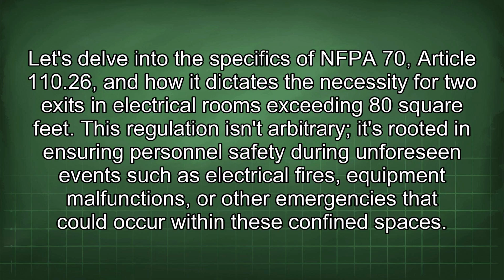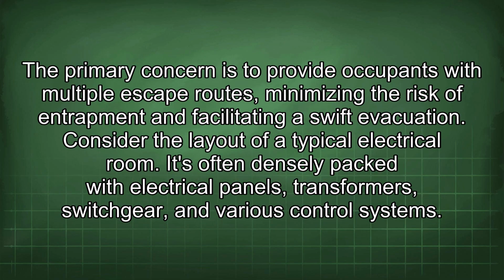Let's delve into the specifics of NFPA 70 Article 110.26 and how it dictates the necessity for 2 exits in electrical rooms exceeding 80 square feet. This regulation isn't arbitrary. It's rooted in ensuring personnel safety during unforeseen events such as electrical fires, equipment malfunctions, or other emergencies that could occur within these confined spaces. The primary concern is to provide occupants with multiple escape routes, minimizing the risk of entrapment and facilitating a swift evacuation. Consider the layout of a typical electrical room.